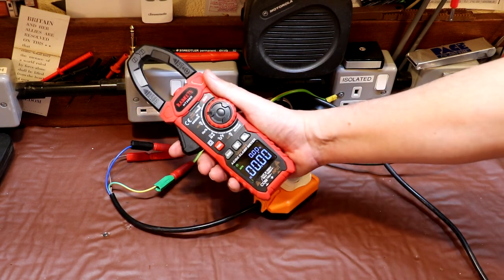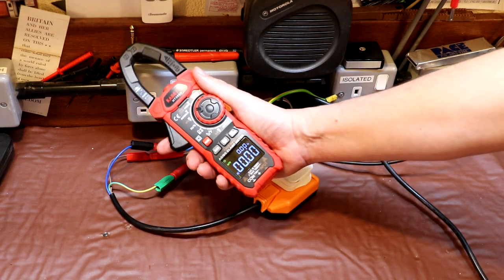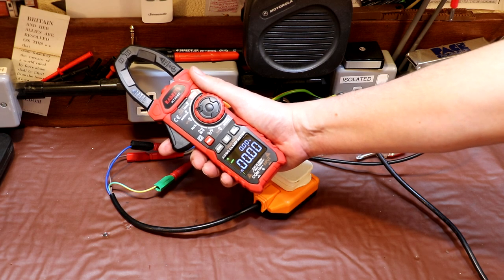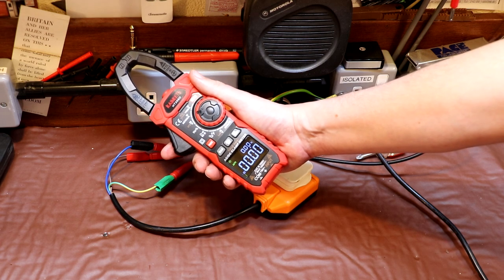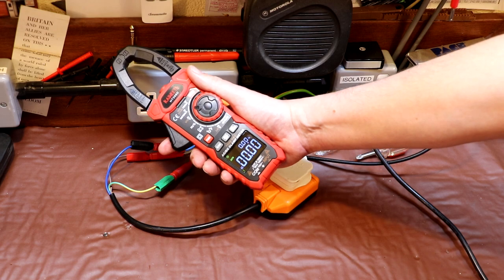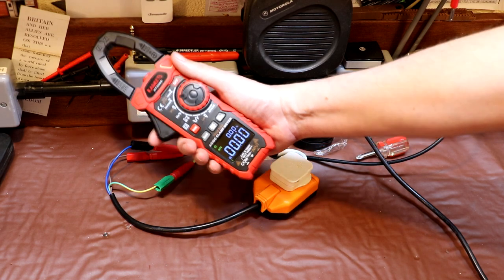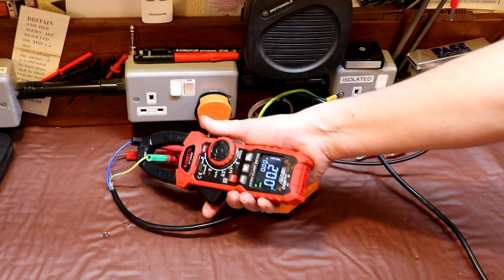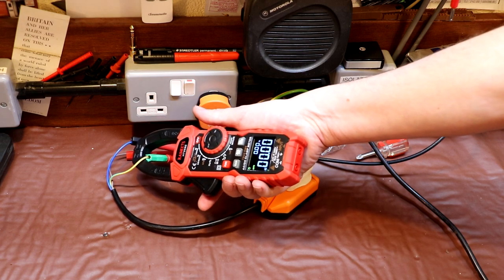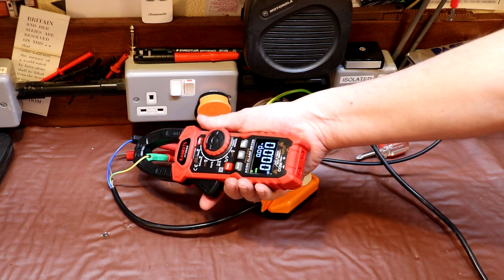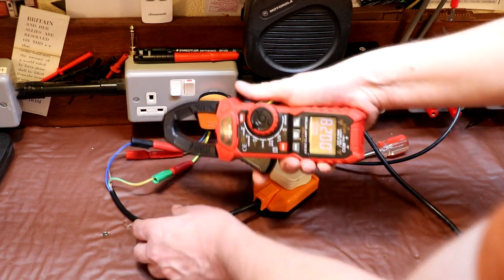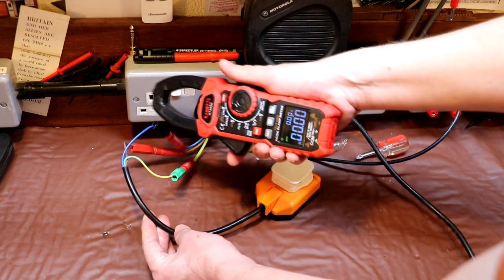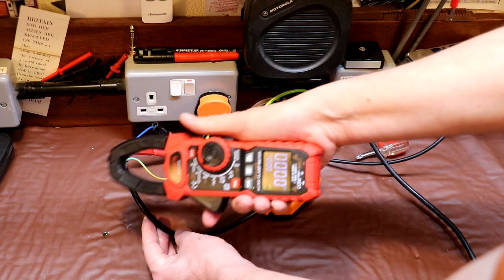Now, some of the main uses that I've had for clamp meters in the past is to track down some of these stray currents and find out why my main supply is tripping out. You may think that the way you would do that is just by clipping onto the earth wire like this, and of course you could do that, but typically that's not the way it's done. A better way is to look for the imbalance in the current flowing into the system and the current flowing out of the system, because they should both be the same.